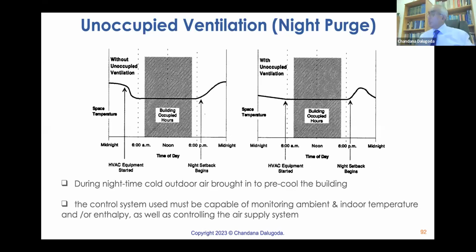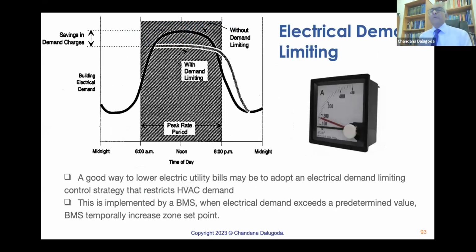Now, with rooftop package units, this is built in. You don't need anything. You don't need a BMS. That has an economizer that will do it automatically. Finally, electrical demand limiting. This is a fantastic BMS control strategy for energy conservation. I'm very unhappy because most building BMS contractors never do these things. A good way to lower electricity utility bills may be to adopt an electrical demand limiting control strategy that restricts the HVAC demand.